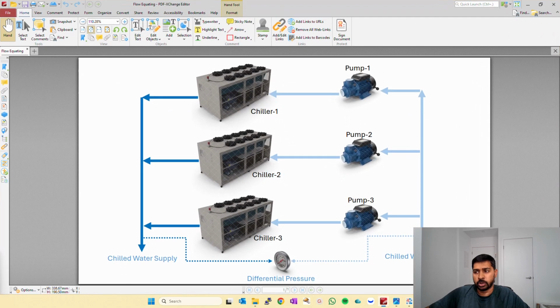I'm creating this video for a specific condition where you will have different flow conditions going to your individual chillers or any other equipment, maybe boilers, and then how to equate those flows. So I'm going to overlay the actual condition that I'm talking about, and then we'll go through the necessary programming steps that you have to take care of so that we maintain the differential pressure that you require, and then equate the flow for all the operating equipment.